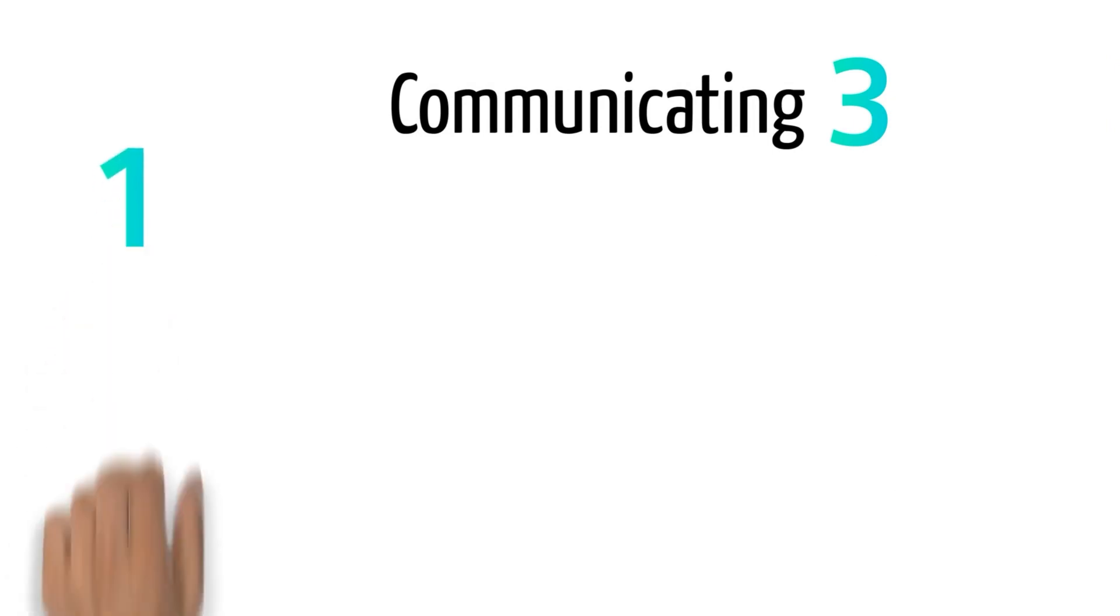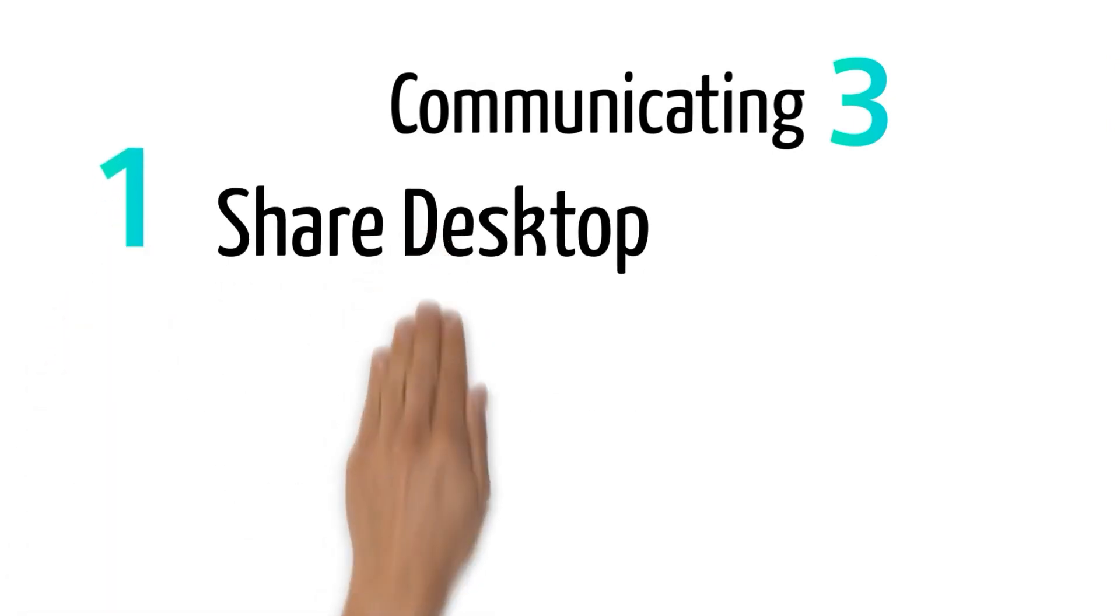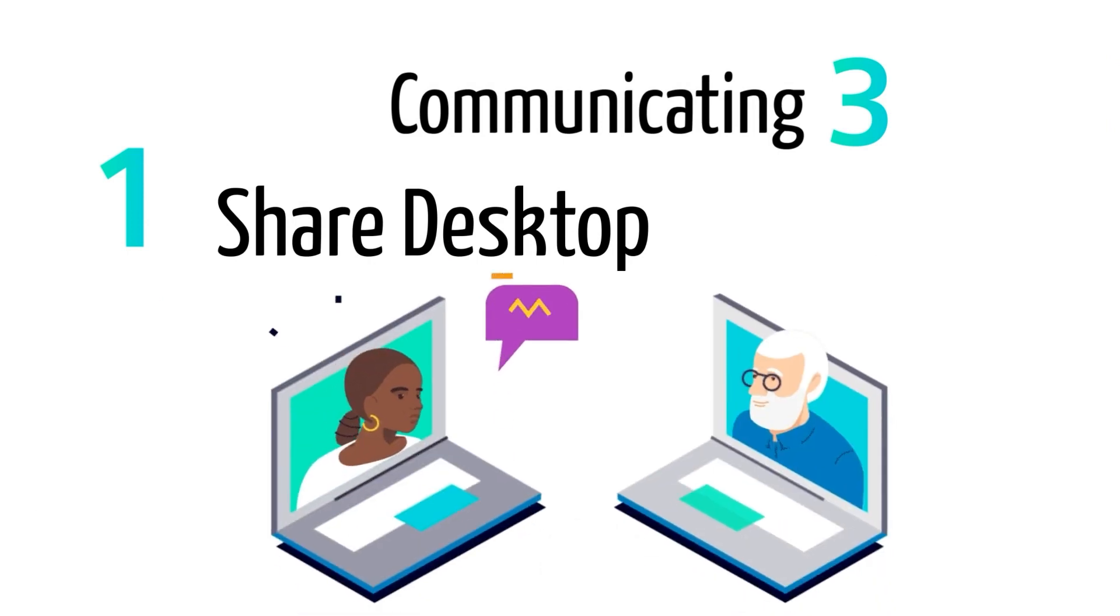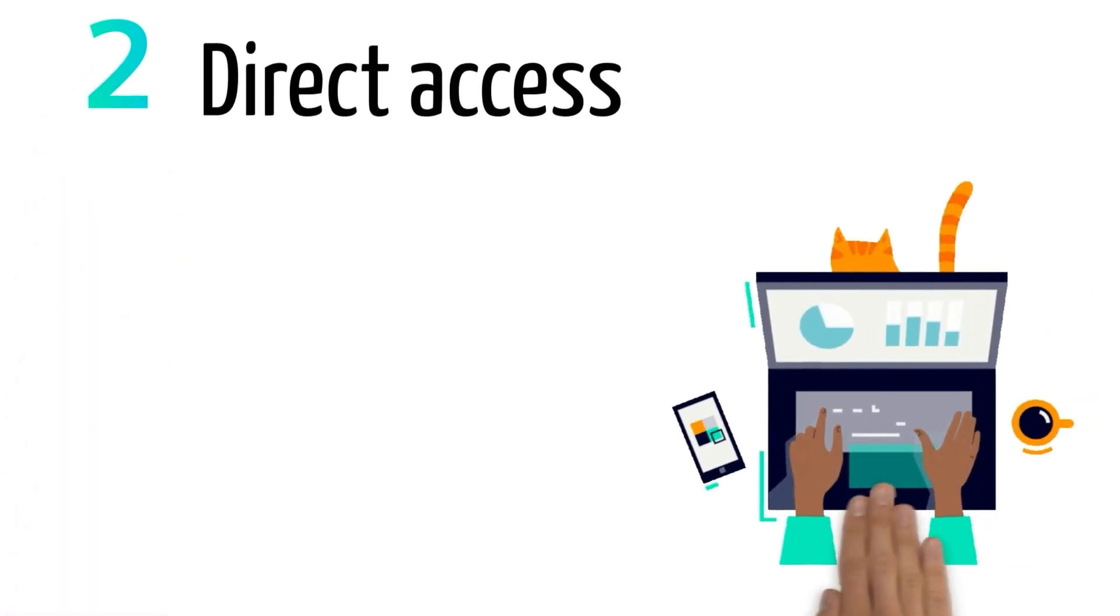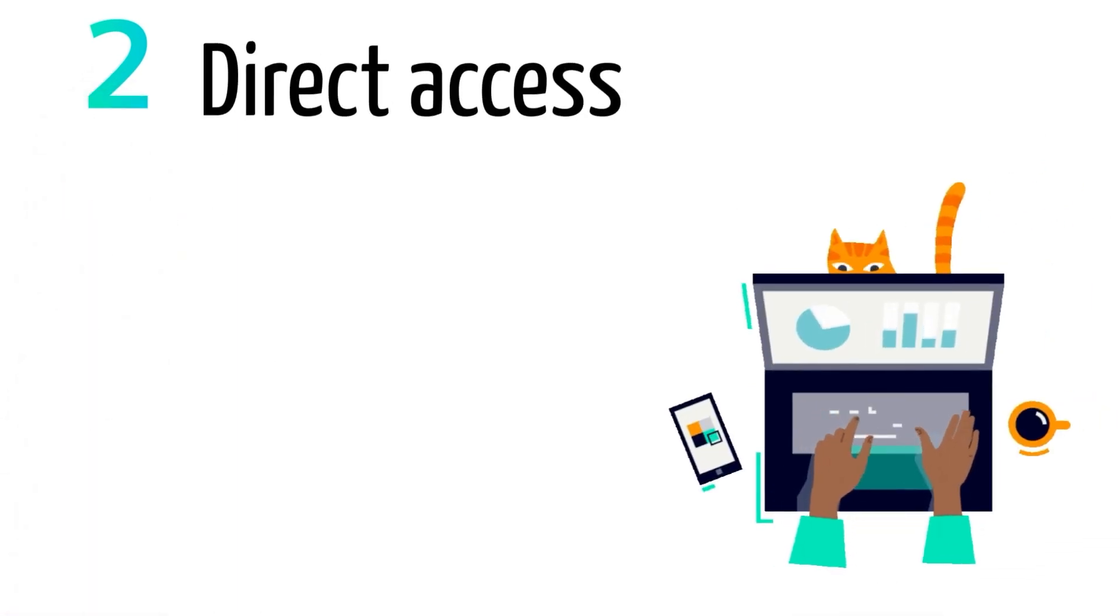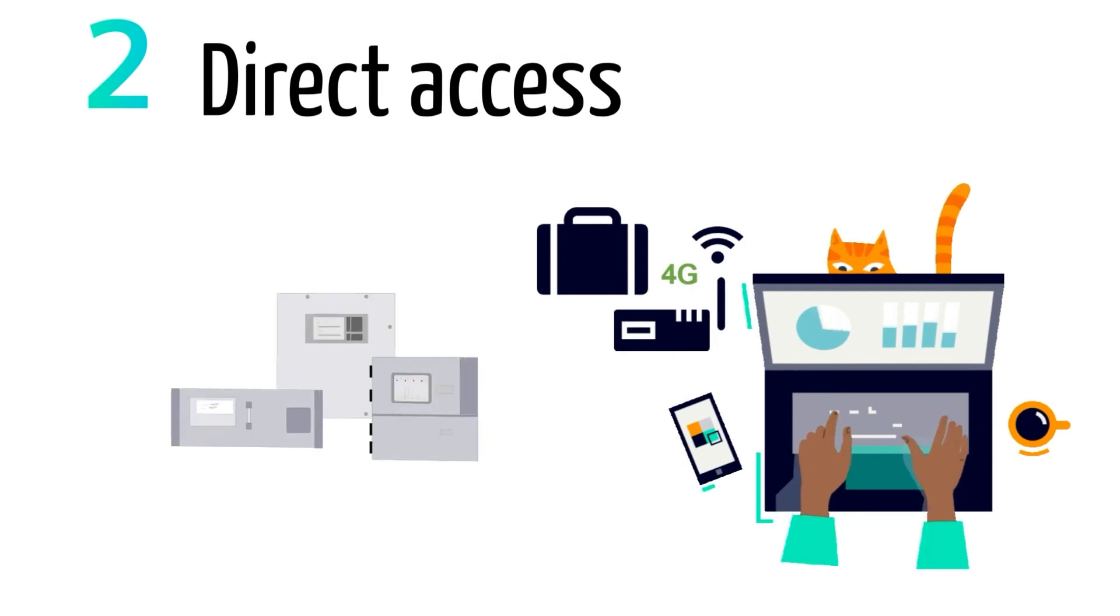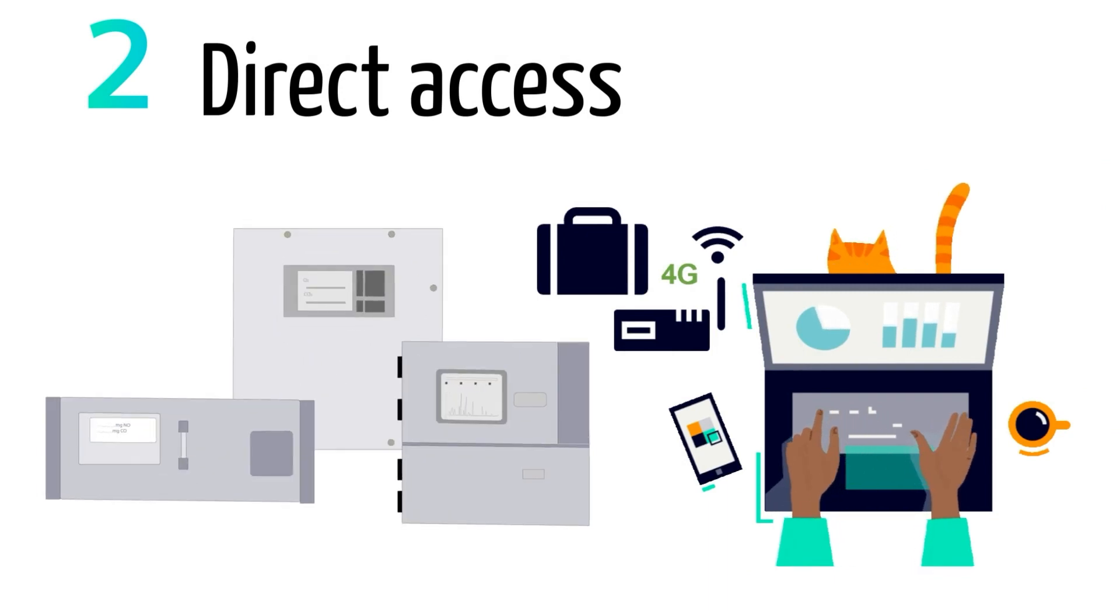First of all, the service engineer team can share their desktop, so a computer to computer screen sharing. Another option is a direct access, which means a communication through a direct connection to the analyzer.